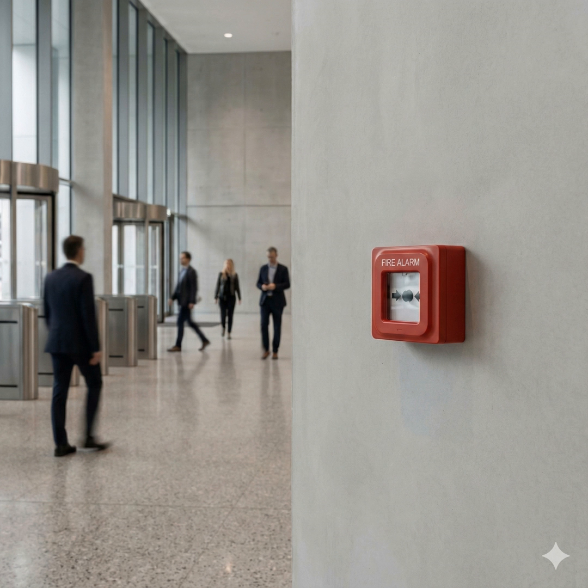Fire safety engineering has to be contextual. The standard spot detector just can't meet the safety needs of a high bay environment. Okay, let's pivot to environments where smoke detection, even with all this tech, is just a bad idea. Think industrial kitchens, boiler rooms, parking garages. Right, the nuisance environments. This is the domain of heat and flame detection. Heat sensors are the necessary fallback for places where cooking aerosols or vehicle exhaust would constantly trigger smoke alarms.